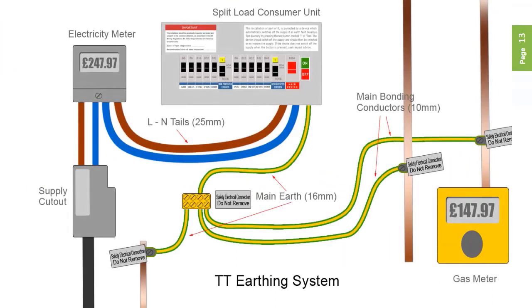TT means terra-terra or earth-earth. This is where no earth conductor is provided by the distributor, and the consumer relies on the actual physical earth to provide the earth protection for the installation, usually through the use of earth rods. Often encountered in rural areas and fed from overhead cables. It's easy to spot, as it requires the installation of an earth electrode or earth rod at the consumer side.